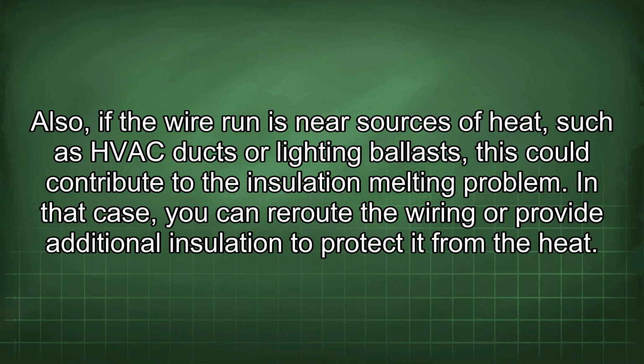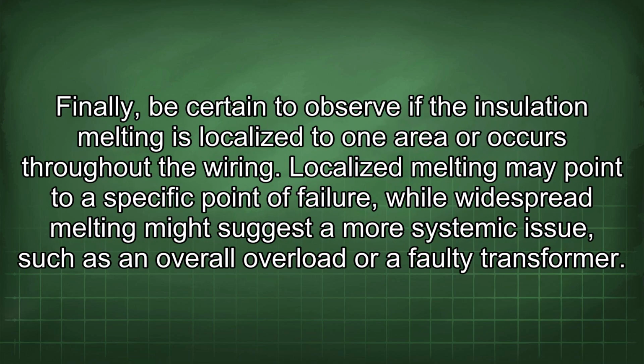In that case, you can reroute the wiring or provide additional insulation to protect it from the heat. Finally, be certain to observe if the insulation melting is localized to one area or occurs throughout the wiring. Localized melting may point to a specific point of failure, while widespread melting might suggest a more systemic issue such as an overall overload or a faulty transformer.